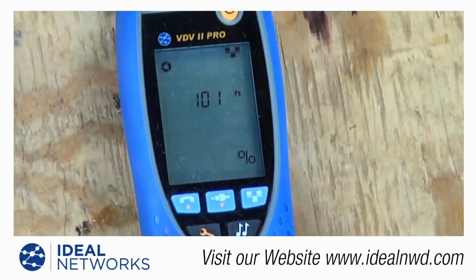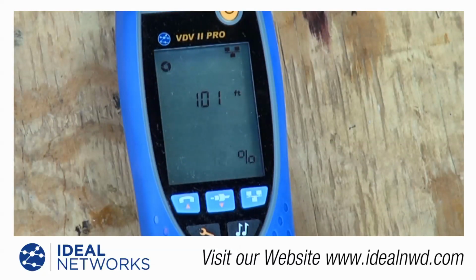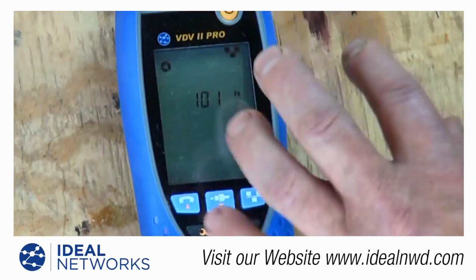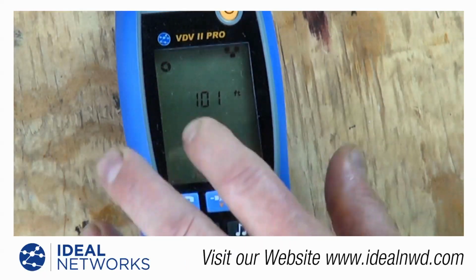If you don't know the NVP of the cable you're dealing with, you can take a known length of cable—we recommend at least 50 feet, longer is better—and adjust the NVP to match that known length by moving the NVP value up and down.